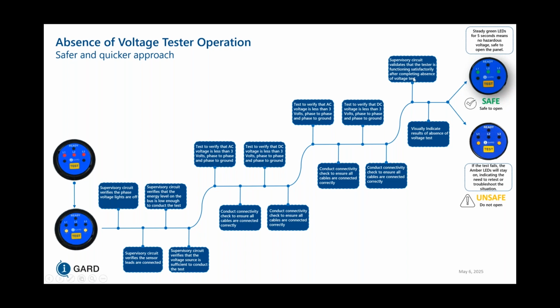And then the supervisory circuit validates that the tester is functioning satisfactorily and completing the absence of voltage test, and then it provides the visual indication of whether there's absence of voltage or not. If there is absence of voltage, then you're going to get 3 green lights. If the absence of voltage test fails, it's going to give yellow lights indicating a caution situation. And this could happen because of a break in the connection or if there is voltage present.